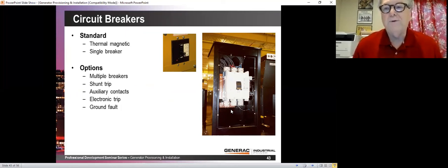I'm going to have to go through some of these fairly fast. This is a pet peeve of mine because circuit breakers, I think, are the biggest scam in the electrical industry. You get a circuit breaker that's not that big and it can cost as much as a car practically. So we tend to say, go with your standard circuit breaker. If it's an 80% circuit breaker, it can still run at 100% in the generator, but only in the generator.